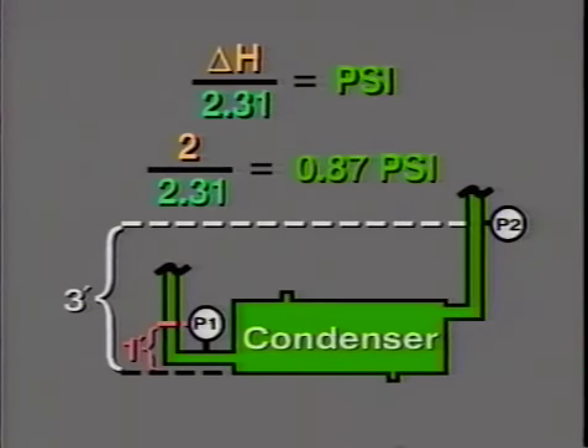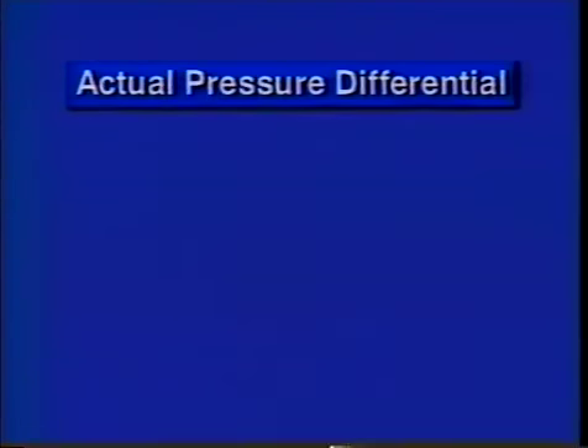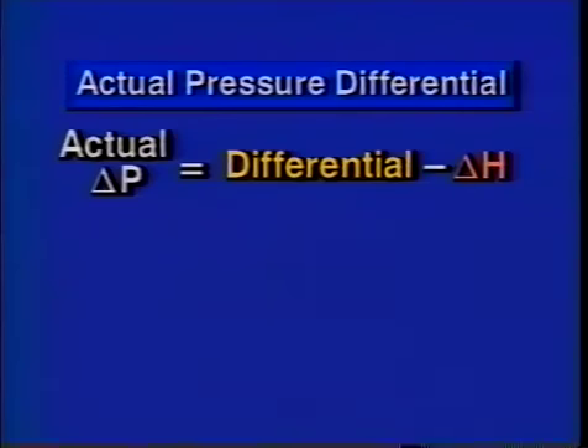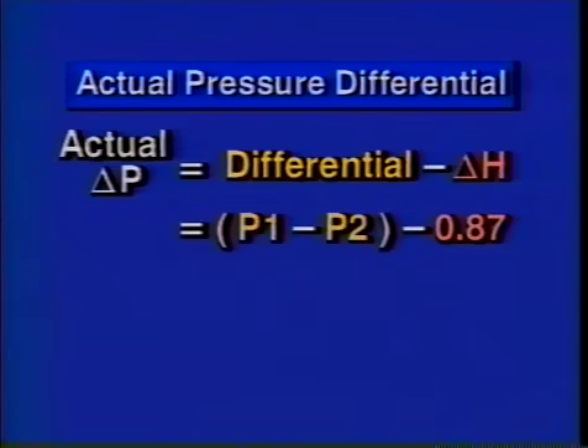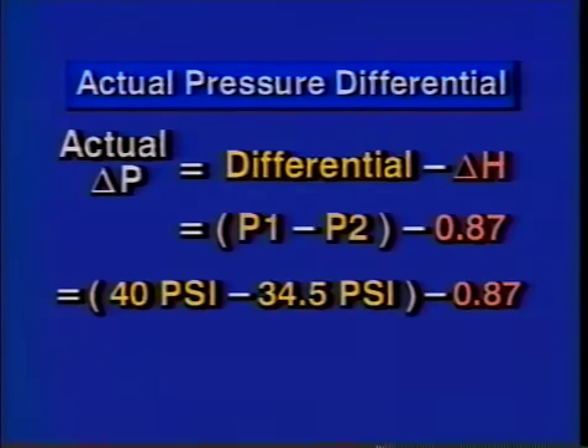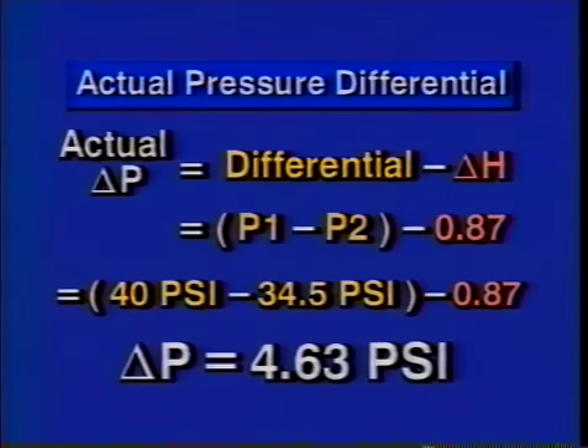Now that we know the height correction factor, we can determine the actual pressure differential with an equation expressed as actual delta P equals differential minus delta H, or delta P equals P1 minus P2 minus 0.87 psi. Remember, the rule of thumb is that we subtract delta H when the entering gauge is lower. Plugging in the numbers for this example, delta P equals 40 psi minus 34.5 psi minus 0.87 psi, which equals 4.63 psi.